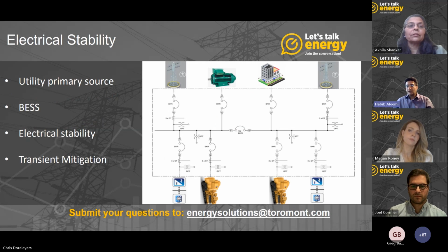In this application, we can see the power system consists of 2 utilities, main-tie-main. We have 2 gas cogenerators, one on each side of a tiebreaker. And then we have 2 battery bank systems, one on each side. Microgrid controller will be used to manage the different power sources. The primary power sources are utility and cogenerators. As we know, gas generators cannot take big step loads. When utility is not available, cogen will provide the power to the load.